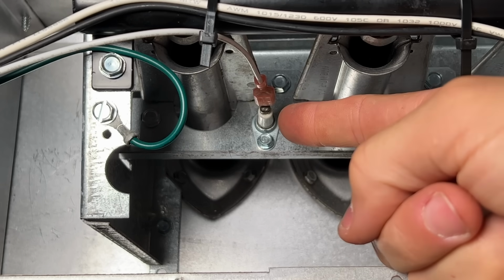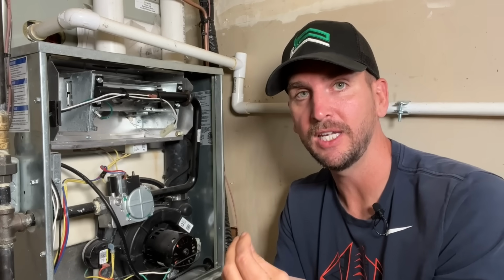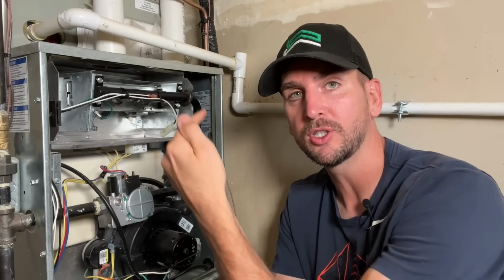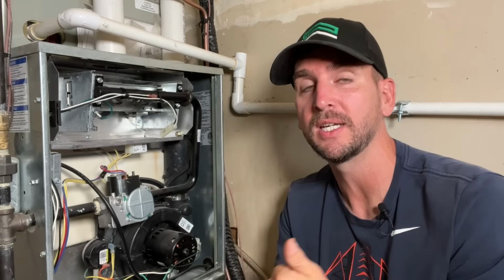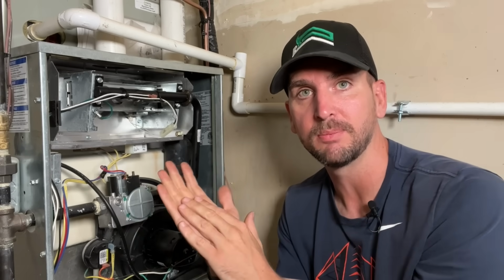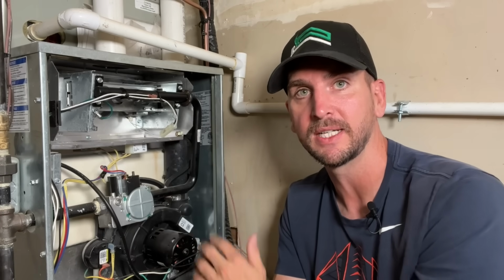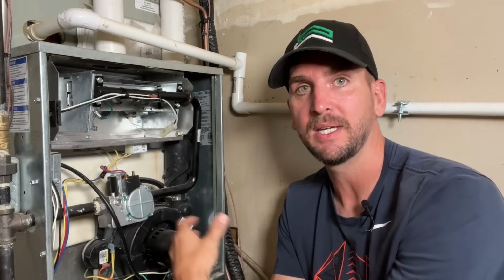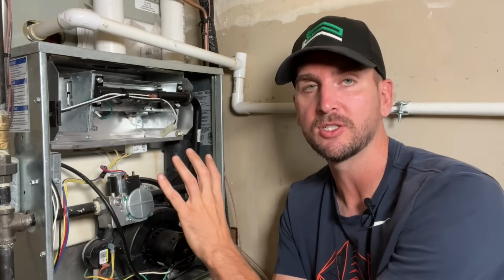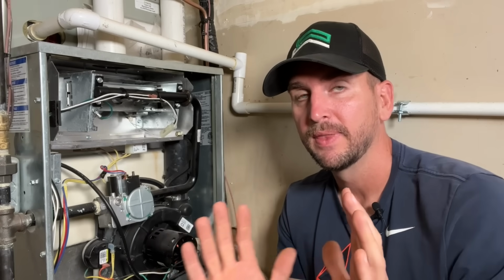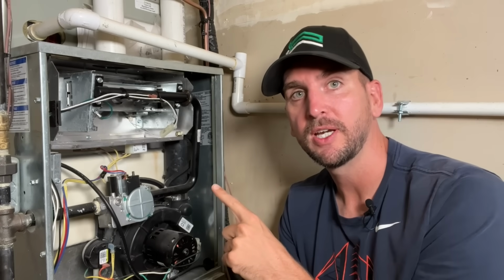So what is the issue? The issue is usually associated right here to the flame detection sensor. For whatever reason, that flame detection sensor is not detecting the flame and providing a small current to your control board saying, yep, we got a flame at the burners, we're good to go on to the next step, which would be heating up that heat exchanger and then the blower fan turning on. But don't worry, this is an easy fix. Let me show you how to remove that.